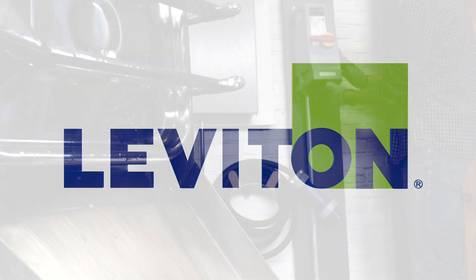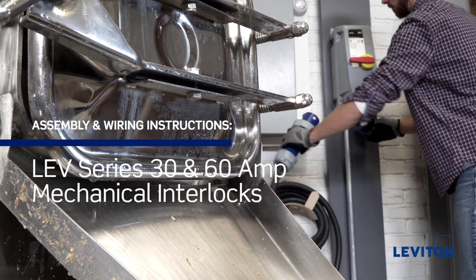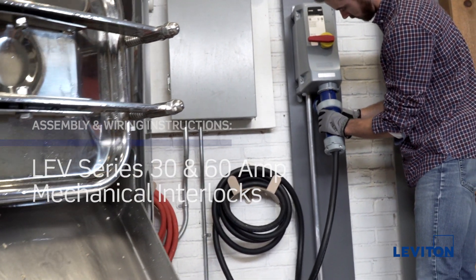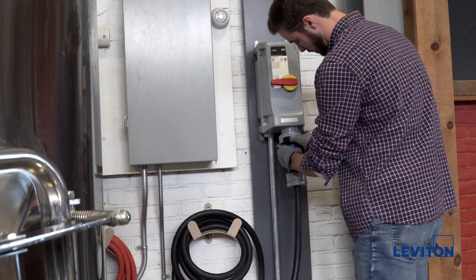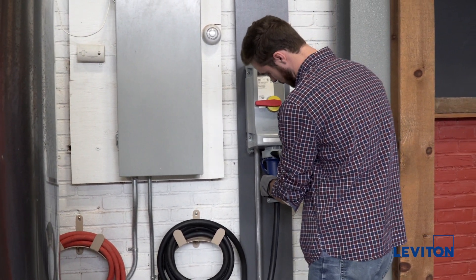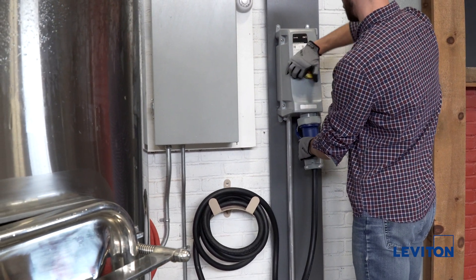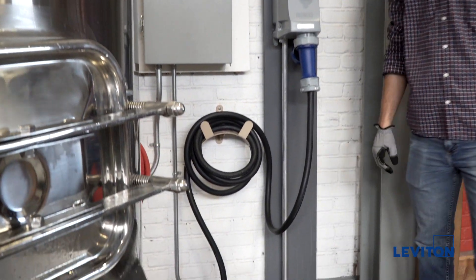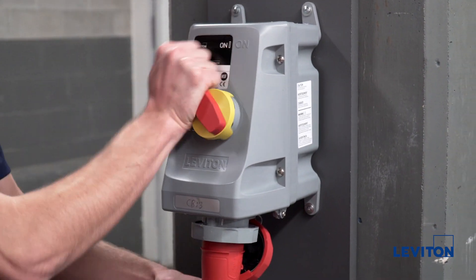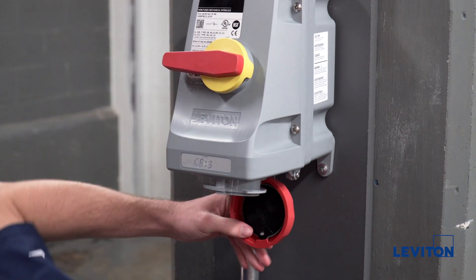In this tutorial we will be demonstrating the proper installation procedure for Leviton's LFV series mechanical interlocks. These devices incorporate a safety disconnect switch and an IEC receptacle in a non-metallic watertight enclosure. The interlock mechanism prevents the making and breaking of power under load by preventing the switch from being put in the on position until an IEC compatible plug is fully inserted. The plug cannot be removed until the switch is in the off position to ensure safety for the operator.